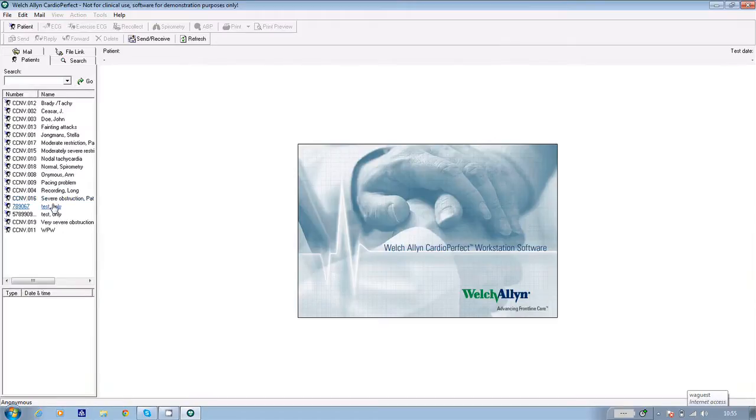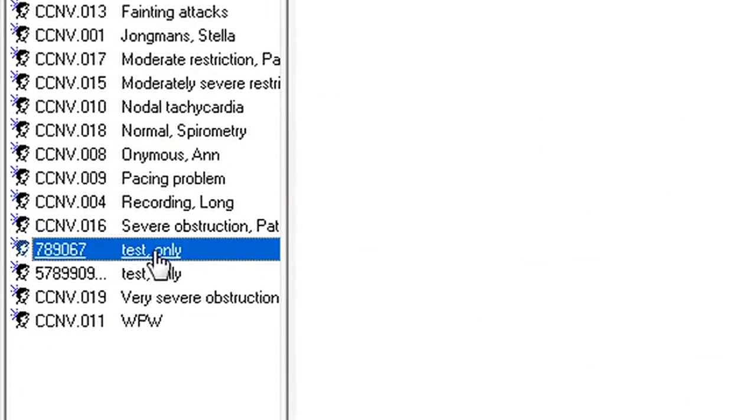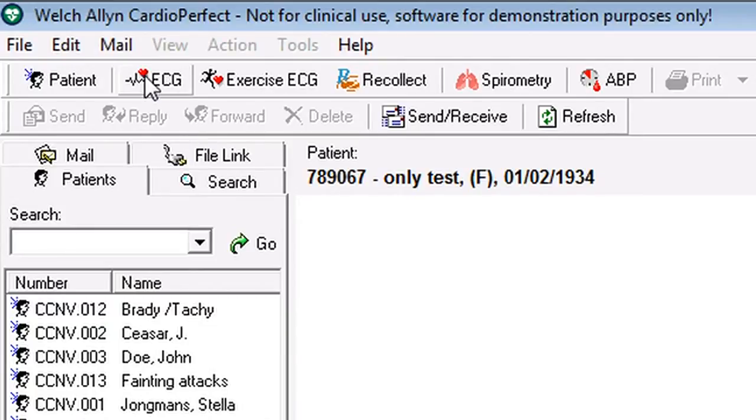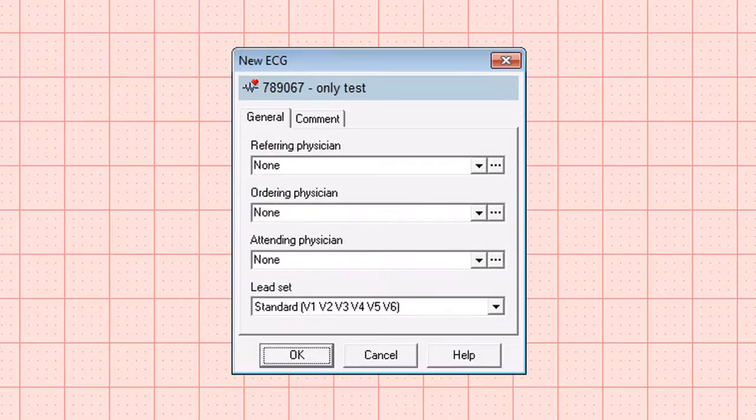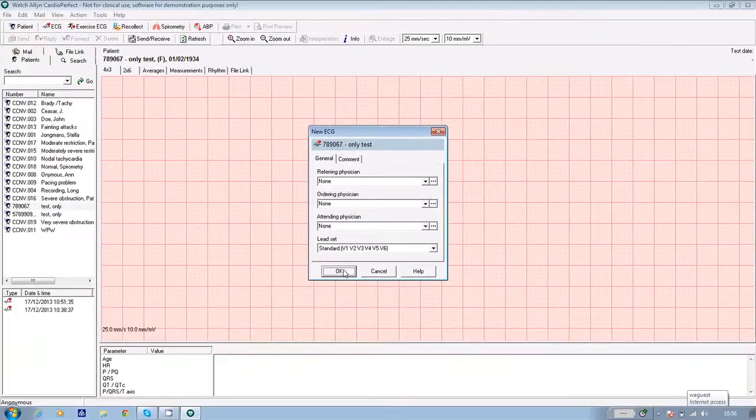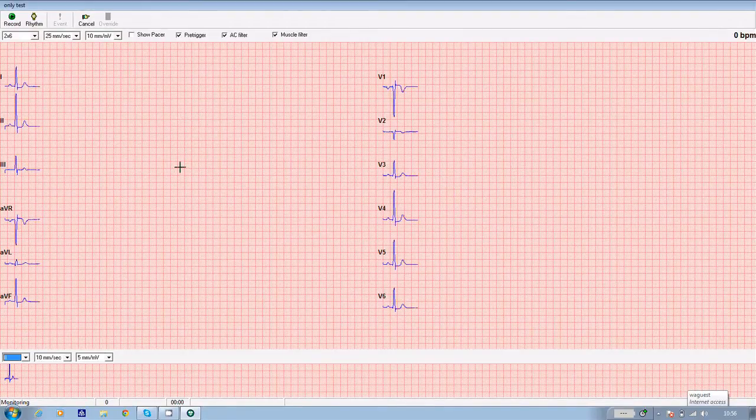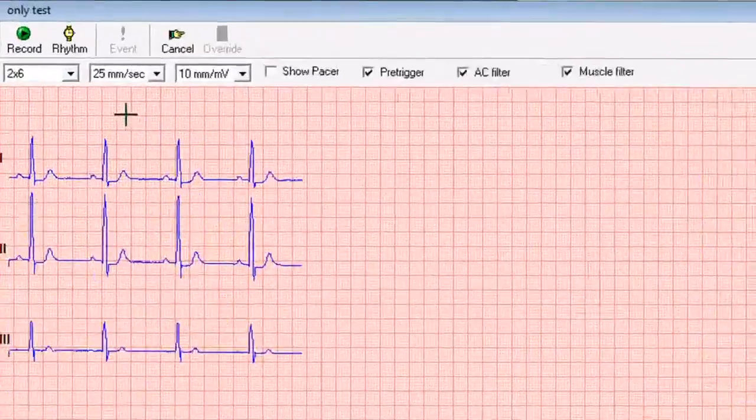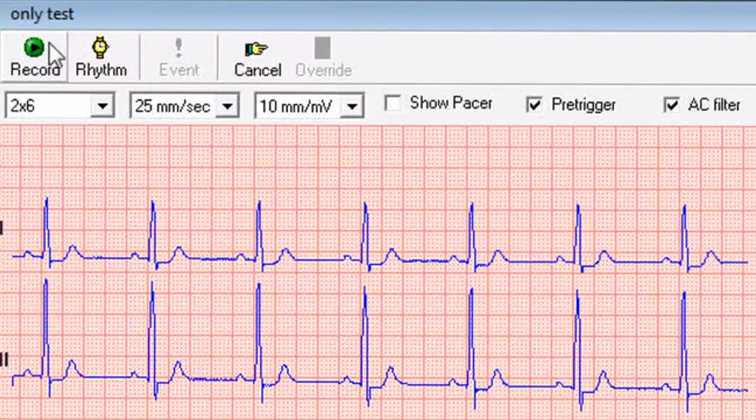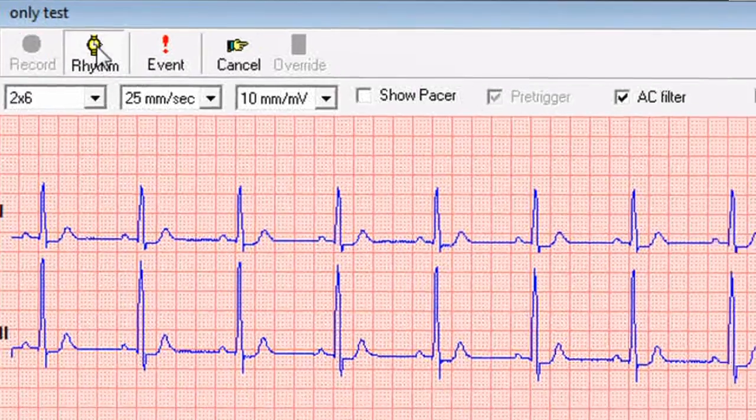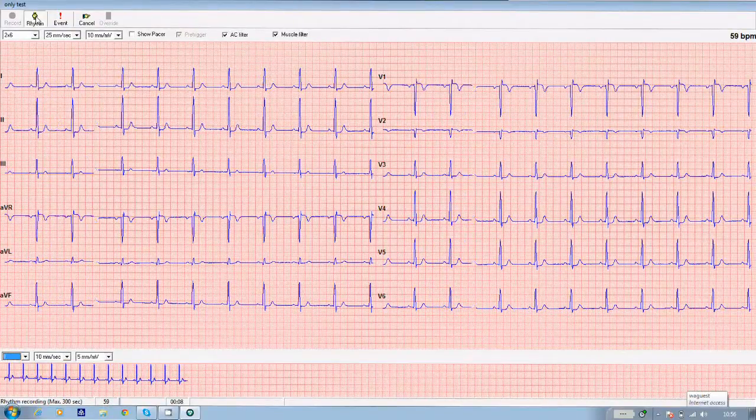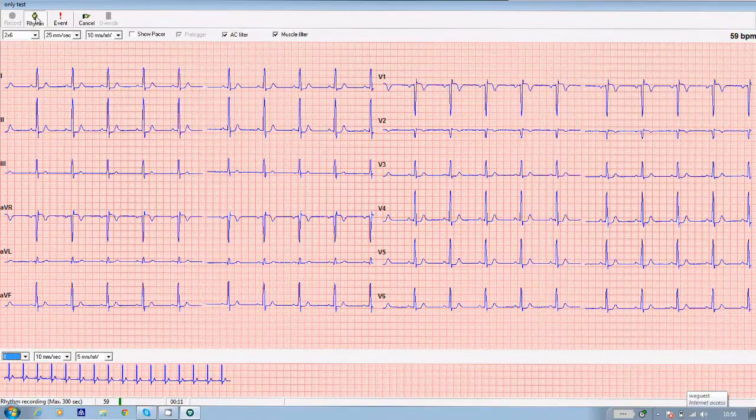But what if you want to take a longer ECG, a rhythm ECG? Well, for this, you need to go back into the software. And again, either input or find your patient. Highlight their name. And again, click on the ECG icon at the top of the screen. Again, you get a box which says new ECG and confirm by clicking OK if the patient's details are correct. Now, once again, the traces appear on the screen in real time. But to take a rhythm ECG, instead of clicking on record in the top left hand corner, click on the rhythm icon next to it. Once you've clicked on that, the software will record five minutes of ECG if you want it to.